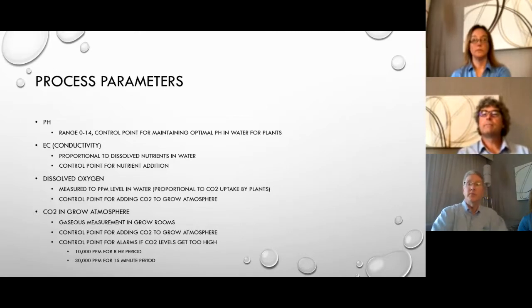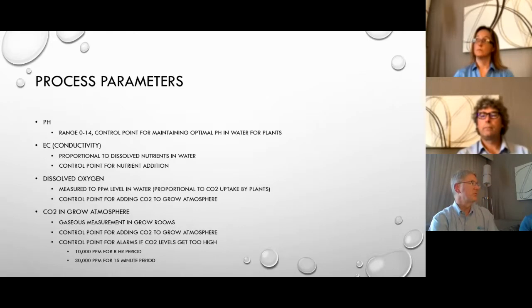Right, and you really should be calibrating based on standards. For example, pH is going to be calibrated against pH standards. Usually you can get standard solutions of 10, 7, or 4. Using any combination of two of those, you can do a 2-point calibration fairly easily on a pH sensor, depending on where you're typically operating, either above or below 7. The electrodeless conductivity, dissolved oxygen, and those others are usually calibrated against handheld instruments that you have calibrated in your lab, and you trust those. So you have to have some kind of calibration standard that you can trust, and then that's what you're setting these instruments against, or calibrating them against.